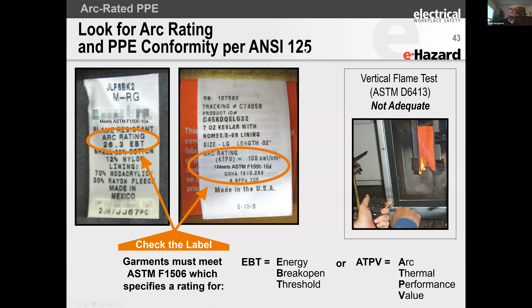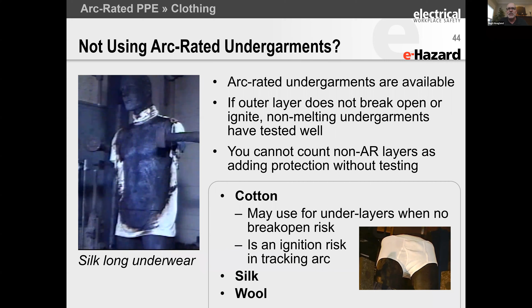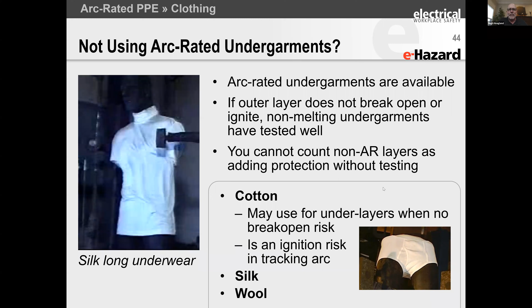Be very careful about not using arc-rated undergarments. This is a silk long john from LL Bean, and I'm going to show you that silk doesn't ignite and continue to burn - so it's almost as if it's arc rated, but it's not very protective. That's one of the negative sides. If you're going to wear undergarments, silk, cotton, and wool are your best options because they naturally have some level of flame resistance - not so much the cotton, but the wool will put itself out, and the silk will put itself out relatively quickly.